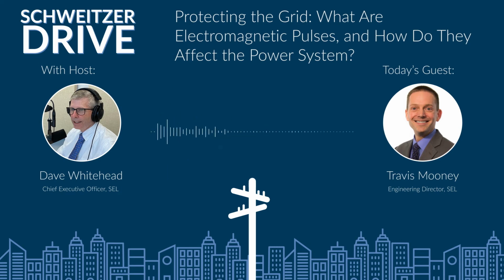The thing that's different about E1 is the extremely high voltage that can happen, around 50 kilovolts per meter. We've tested our relays at third-party labs, subjecting them directly to an electromagnetic field of 50 kilovolts per meter, and that's a lot. A typical walkie-talkie antenna is around 10 to 30 volts per meter - here we're testing at 50 kilovolts per meter, three orders of magnitude larger.